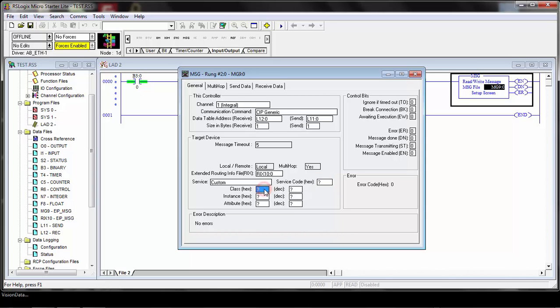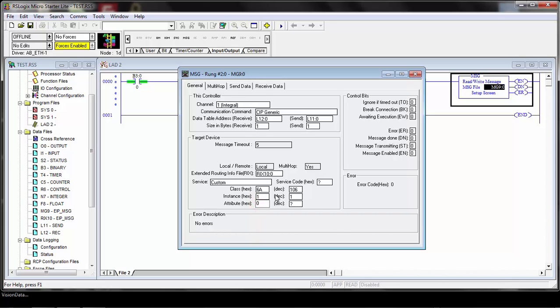For the standard items, the class ID is common or the same for any CVX message. For the CVX series, it's 6A hex. That's the class ID you want to put in there. The instance will be 1 and then put in a 0 for the attribute. This is how you'll be setting up all the custom service messages. The service code is going to depend on the message, which will be shown in the specific examples as well as the size of the send and receive information.